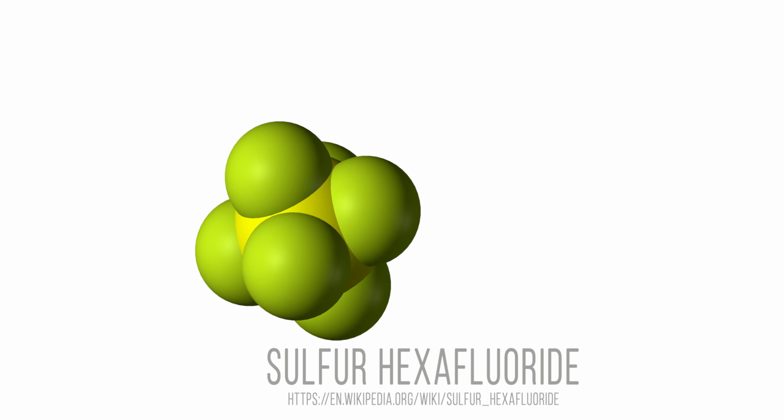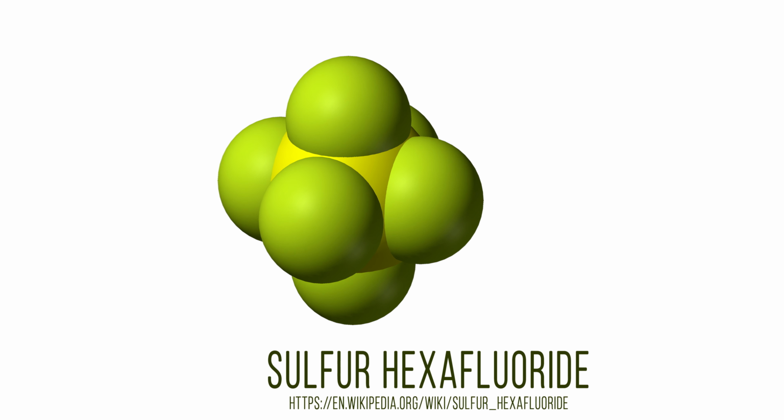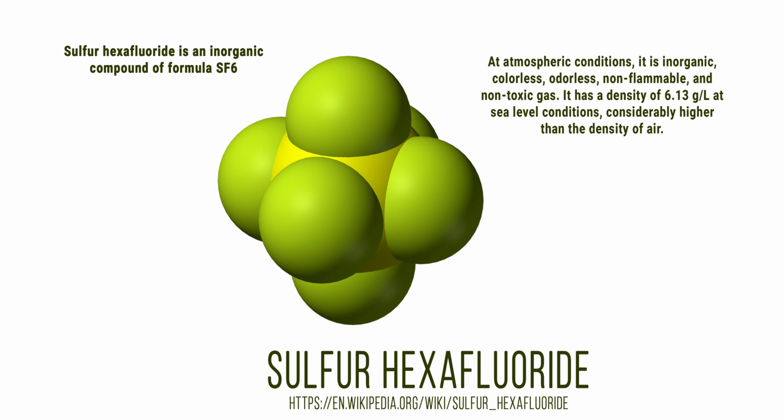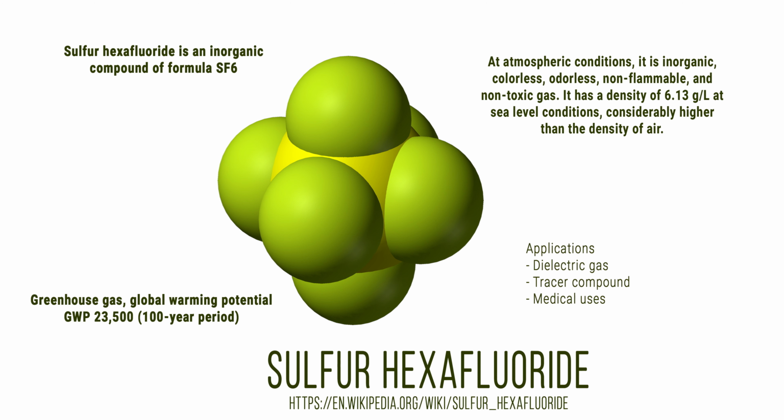The fluid that fills the measurement tube is sulfur hexafluoride. This is an inorganic compound whose formula is SF6. In gas state, it shows a high dielectric resistance, being a good insulator. Due to this, the fluid is commonly used as insulation in electric distribution systems, especially in high voltage. Sulfur hexafluoride is also used in some steel industry processes, as well as in eye surgery.